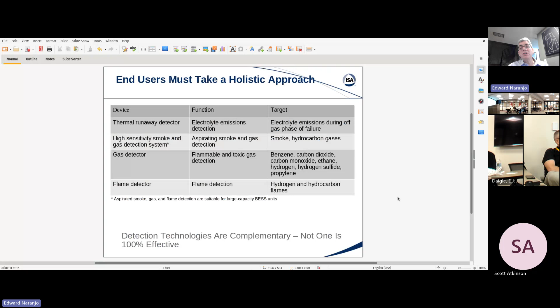By the time hydrogen sulfide can burn, the concentration is well above levels that can kill a human being. Lastly, we have flame detection, which will always have a place in a BESS container unit under NFPA 855. Keep in mind that detection technologies are complementary. Each has its own deficiencies, but because these methods tend to be independent, sharing few common failures, they can serve as additional layers of protection.